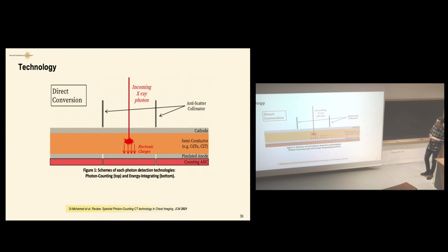In a pixel detector, more than 6 million photons per millimeter square per second are hitting the pixel. These detectors will take care of the energy of each photon, with some spectral distortion, but anyway, they take charge of this energy resolving aspect, so that we can use it as a more detailed description of the X-ray spectrum.